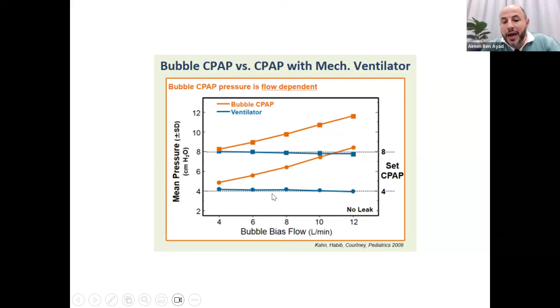So the study measured bubble CPAP versus ventilator CPAP. Here on the y-axis, you have the mean airway pressure. On the x-axis, you have the flow. The constant machine or conventional CPAP is constant. The blue, if you set 4, it's constant 4, rate and pressure. But with bubble CPAP, you can control it. The higher you go in the flow, the higher the pressure you might get.